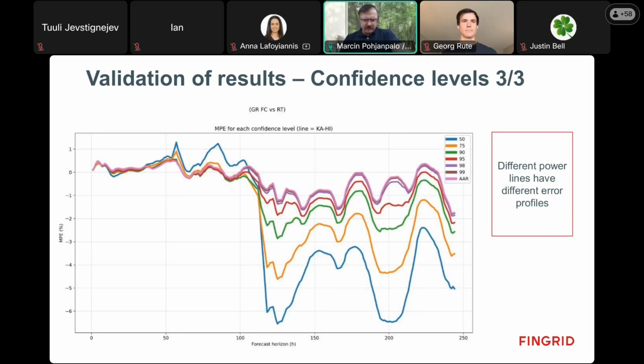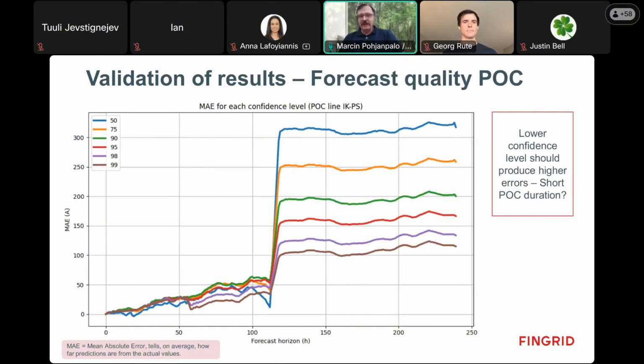Yeah, I think you should have one more about the mean errors. So there we go - this is the absolute error. Here you just want to compare the proof of concept to the site acceptance test. The problem with absolute errors is it depends completely on the line and what conductor you have, etc. So I personally prefer the mean percentage errors, because there I can actually see how much I care about it, since it's usually below 2%, and that's usually good enough. If you see higher errors than that, I start wondering what's going on there.